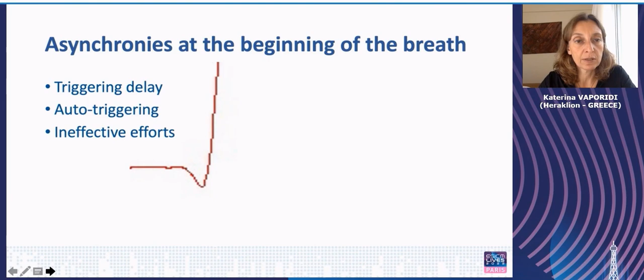Obviously, as the ventilator needs to understand that the patient effort has begun, there will be some delay in this procedure. Triggering delay depends on patient effort, the presence of intrinsic PEEP, the triggering threshold that we have set, and the valve response time, so something of the manufacturer of the ventilator. Bench studies indicate that triggering delay of the ventilators we currently use in our ICUs is between 50 and 100 milliseconds. Clinical studies, though, indicate that this time interval may be more, about 100 to 200 milliseconds.